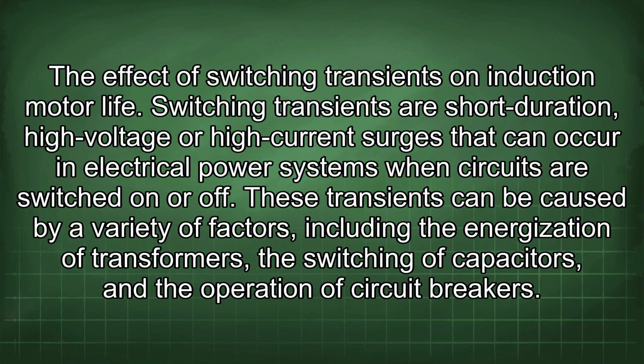The effect of switching transients on induction motor life. Switching transients are short-duration, high-voltage or high-current surges that can occur in electrical power systems when circuits are switched on or off. These transients can be caused by a variety of factors, including the energization of transformers, the switching of capacitors, and the operation of circuit breakers.